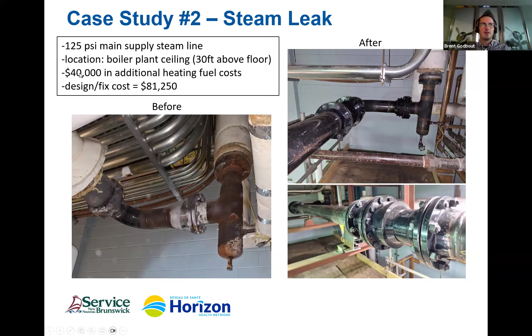We had to stage up to this, obviously. The reason we found it is because it got so bad that it started dripping down to the floor. Once we saw the condensate dripping down on the floor, that's why we staged up to it and found it. The fix was about $81,000 to get this fixed, but like I said, we were losing about $40,000 a year, so it paid for itself in a couple of years.